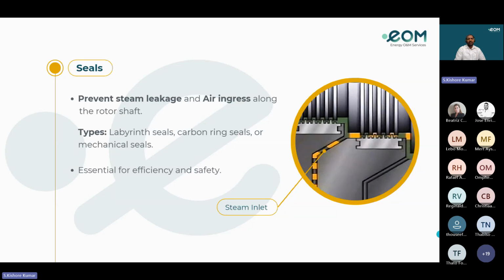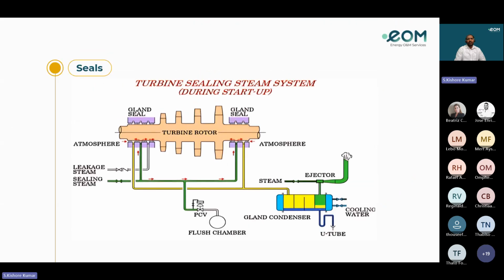Here we can see the steam inlet in this image. In this image, we can see the typical sealing system. At the high pressure end, sealing steam is injected inward toward the turbine to block outward steam leakage. At the low pressure end, sealing steam is injected outward to block air from entering the casing under vacuum conditions. The leak-off steam is drawn from the middle of the gland and sent to the gland steam condenser.